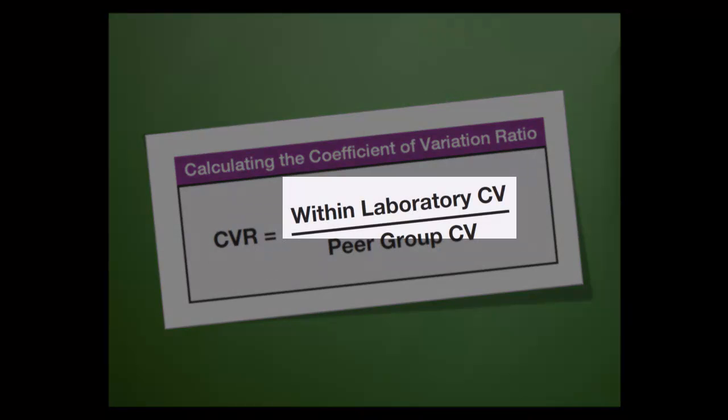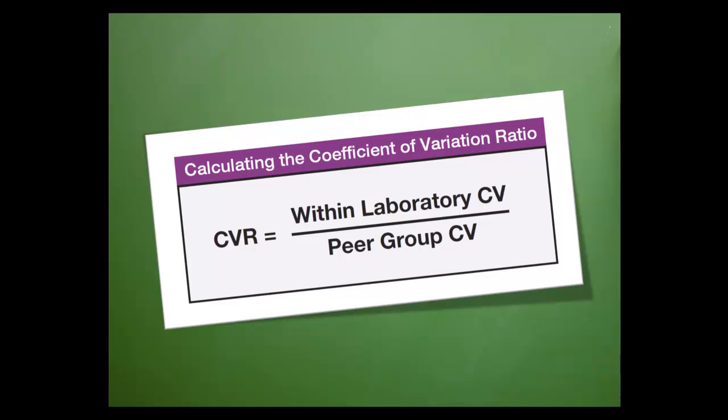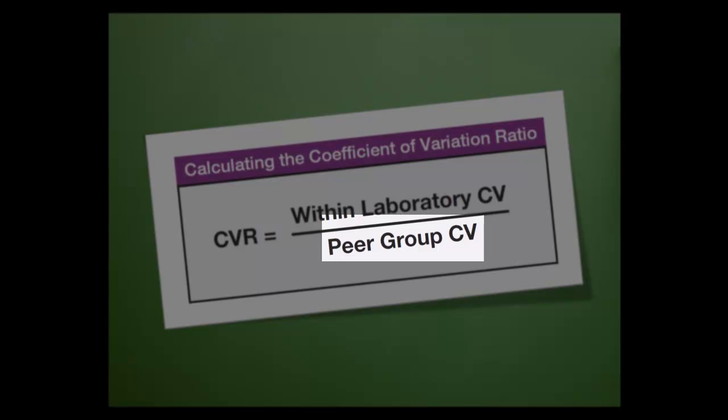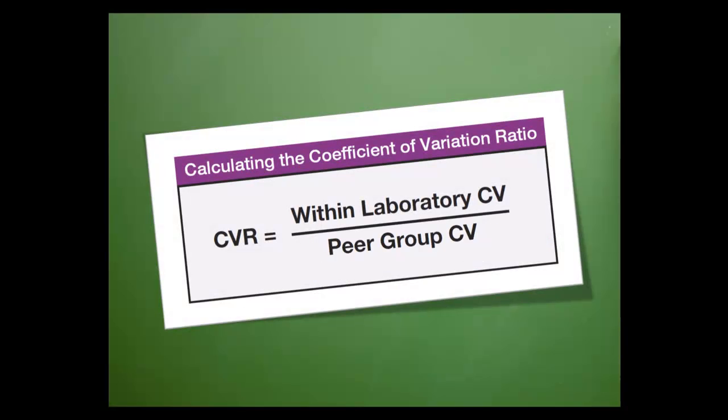First we need the within laboratory CV. I encourage you to take a look at our video for calculating CV if you need additional information. The within laboratory CV will be divided by the peer group CV. The peer group CV can be obtained from an interlaboratory comparison report.